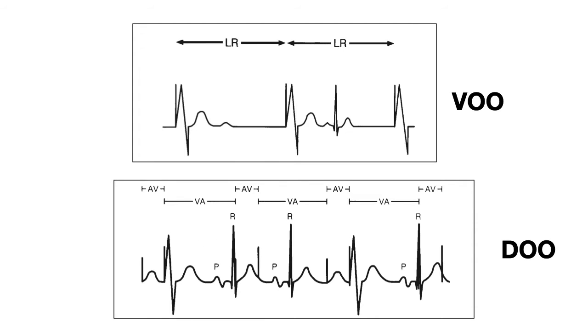Here in this example, we start with the simplest form of all the pacing modes, which is the VOO, or ventricular asynchronous mode. There is no sensing here, nor mode of response. The timing cycles of the asynchronous pacing consist of only a programmed rate, and the pacemaker delivers the ventricular pacing artifact at this programmed rate regardless of any intrinsic activities.